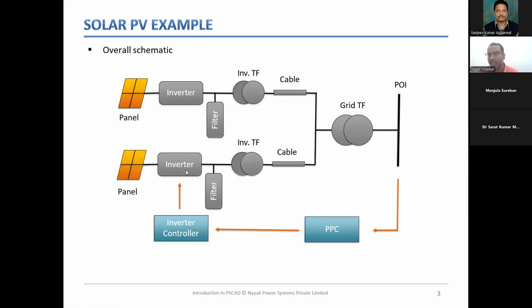Okay. So if you notice here, there are a number of converters. They have their own inverter controllers. So there should be one more controller that is controlling the entire power output of the plant, or the entire behavior of the plant. And that task is done by this component called the PPC, or power plant controller. So this PPC is like a supervisory control. The operator sits at a location where the PPC is remotely accessible, and he asks the plant to generate certain active and reactive power, right? So this PPC requires set points from the plant operator, and it requires measurement, and that measurement will come from the regulated bus. In our case, it will be your point of interconnection, POI.